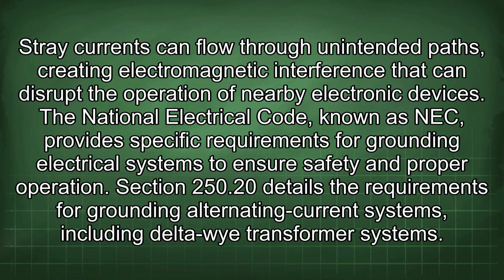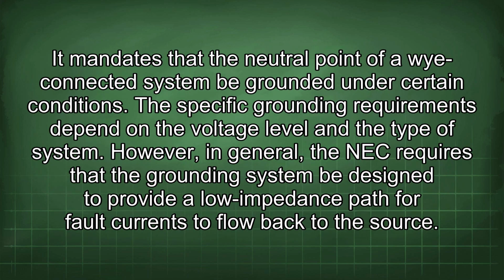The National Electrical Code, known as NEC, provides specific requirements for grounding electrical systems to ensure safety and proper operation. Section 250.20 details the requirements for grounding alternating current systems, including delta-wye transformer systems. It mandates that the neutral point of a Y-connected system be grounded under certain conditions. The specific grounding requirements depend on the voltage level and the type of system. However, in general, the NEC requires that the grounding system be designed to provide a low impedance path for fault currents to flow back to the source.